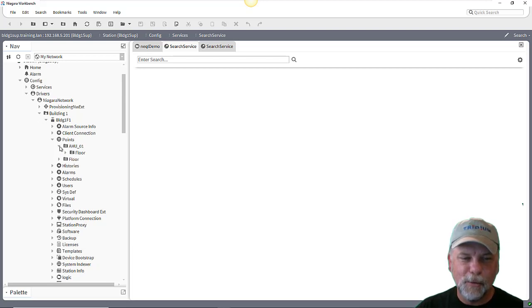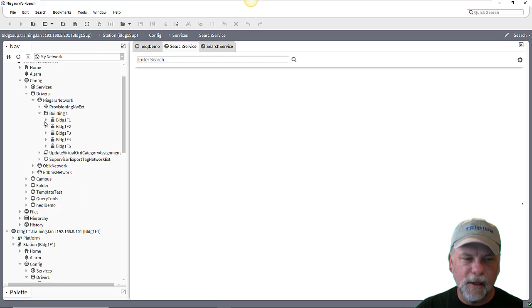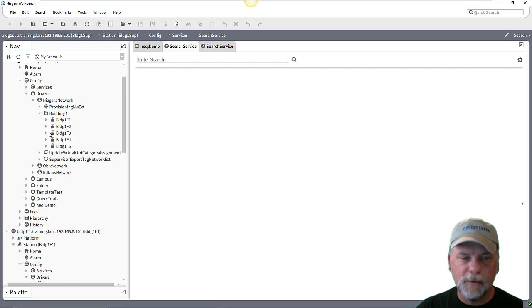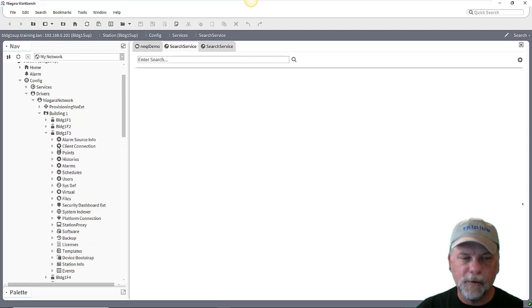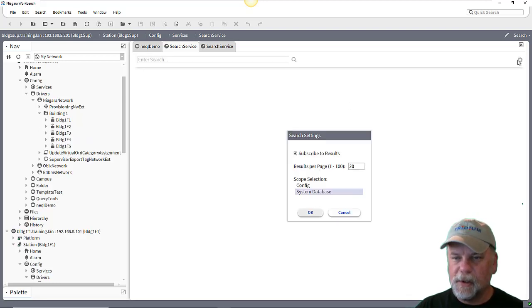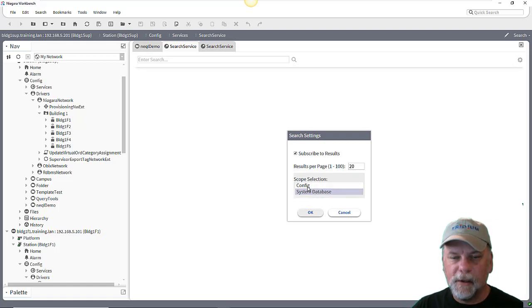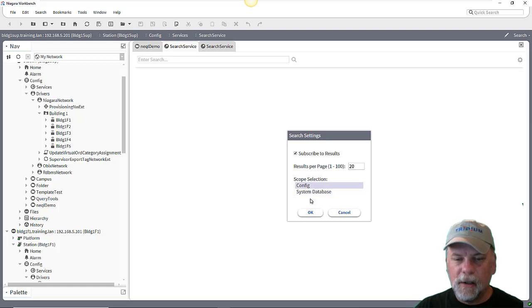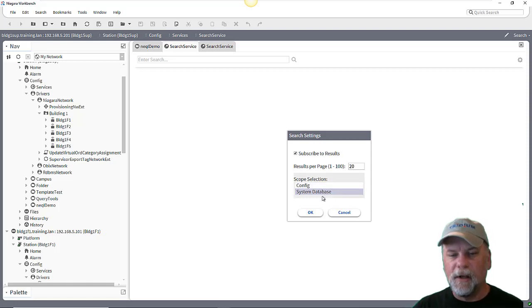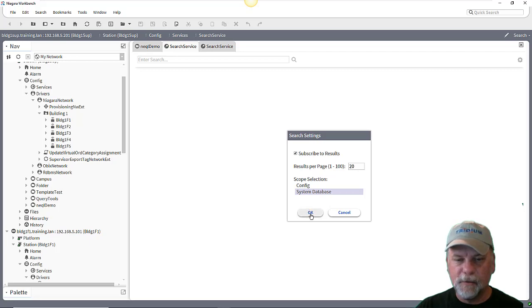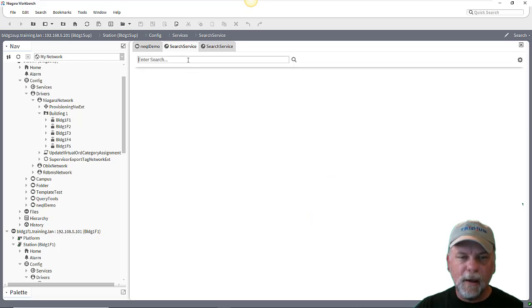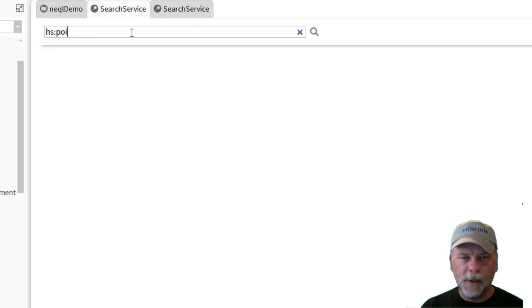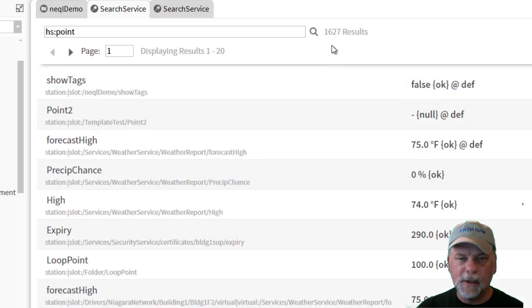So if I look at the points container here there's actually a total lot. There are a few points mapped in here for one of the devices, but none of the other devices, either air handler two doesn't have our building floor two and floor three and so forth, there's no points mapped in. When you're looking in the search service and you configure with the gear icon, the scope selection can be the config which is that station space or in this case just system database, or you can have multiples selected there holding the control key or the shift key. So what I've done is just set this to search the system database only, not the local station in the supervisor.